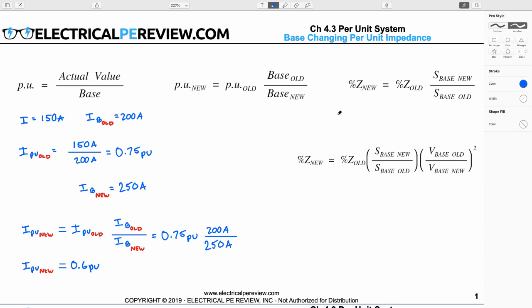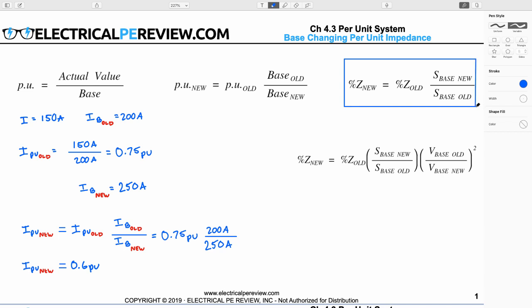Now, the question is: most often in books we see a formula that looks backwards. When we base change percent impedance, instead of saying our new base on bottom and our old base on top, we see a new power base on top and an old power base on bottom — it looks backwards. Our percent impedance new equals our percent impedance old, except this time our new base is on top and our old base is on bottom. It appears to be backwards from the formula we just used. So what's going on?